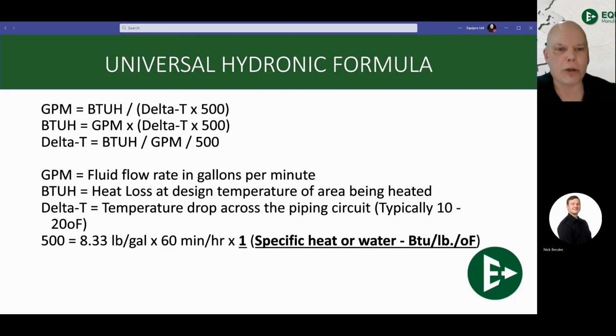GPM comes up all the time in hydronics. That's our flow. How fast is our water going? Do we need to move the water at 5 GPM or 10 GPM, or in most cases 1 or 2 GPM to heat the area? How we calculate GPM is BTU divided by delta T times 500. Your delta T is your temperature drop across your piping circuit. It's usually 10 degrees in radiant in-floor and 20 degrees in pretty much everything else. So GPM equals BTU divided by delta T times 500. That's your standard calculation for calculating flow to deliver a certain amount of BTUs.